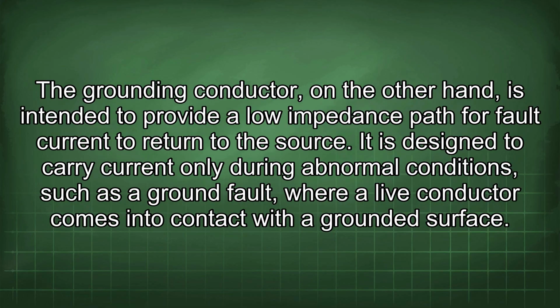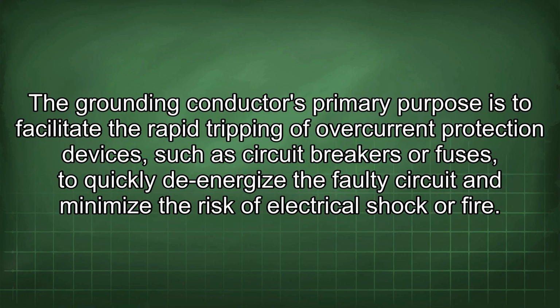The grounding conductor, on the other hand, is intended to provide a low impedance path for fault current to return to the source. It is designed to carry current only during abnormal conditions, such as a ground fault, where a live conductor comes into contact with a grounded surface. The grounding conductor's primary purpose is to facilitate the rapid tripping of overcurrent protection devices such as circuit breakers or fuses to quickly de-energize a faulty circuit and minimize the risk of electrical shock or fire.